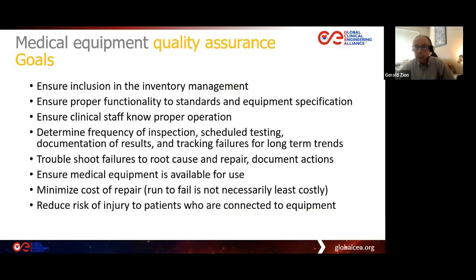So here are some goals. We want to ensure the inclusion and the proper onboarding of any medical device that we will hold in the inventory of our hospital biomed department or our client site if we're field service or traveling. We want to ensure proper functionality to the standards and to the manufacturer's equipment specification. We want to ensure clinical staff know how to properly operate the medical equipment. Bear in mind that clinical staff sometimes are brought on as temporary additions or may come from some other hospital or location that is using a different brand and model of a category of medical device, and therefore may not be properly familiar with the brands and models that are in our inventory at our location.